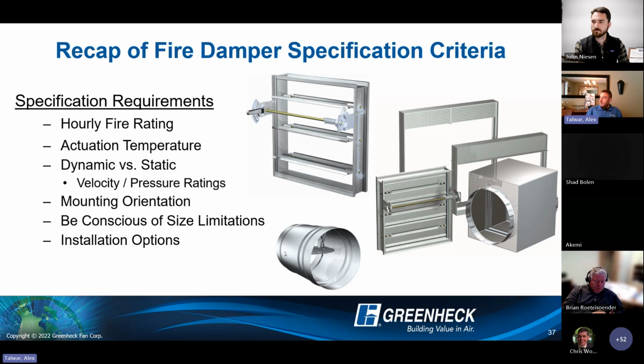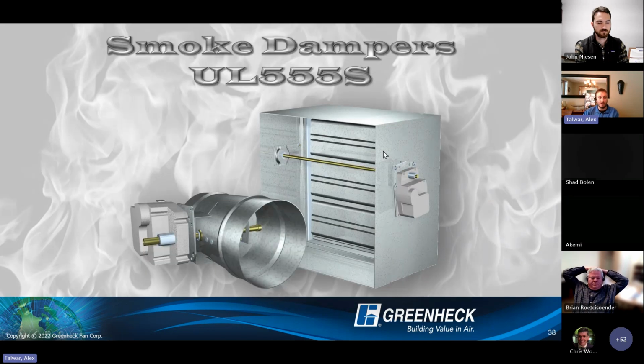So recapping the fire damper criteria, I think I'm actually doing pretty good here. Fire rating, 1.5 or 3 hours. Actuation temperature, fusible link melting temperature, 165 standard. Do you need to go higher than that if you have heated air? Something to consider. Your velocity and pressure ratings for the dynamic rated products versus a static rated product that is not tested to close against airflow. Importance of mounting orientation, vertical or horizontal. And then just being aware of size limitations on these products. Again, having to pass the fire test always is a difficult thing. So just be aware that those things exist.